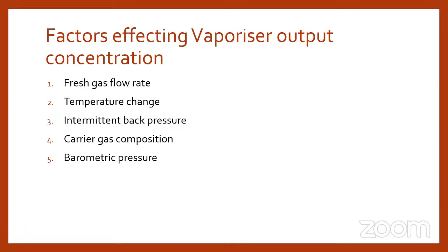The factors affecting the vaporizer output concentration are fresh gas flow rate, temperature change, intermittent back pressure, carrier gas composition, and barometric pressure. When we come to the fresh gas flow rate, if the flow rate is high, then the output will also be high, because the flow of fresh gas entering the vaporizing chamber will be more. So the vapor that mixes with the fresh gas will be more, and the output will be more. And vice versa, if the flow rate is low, then the vaporizer output concentration will also be low.